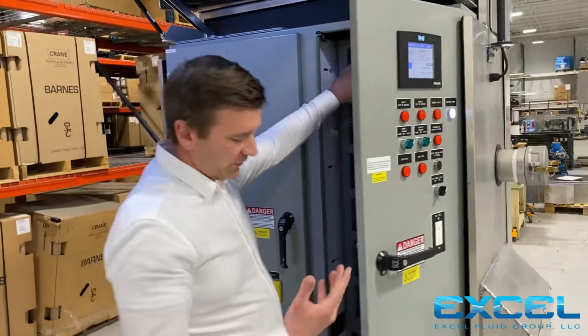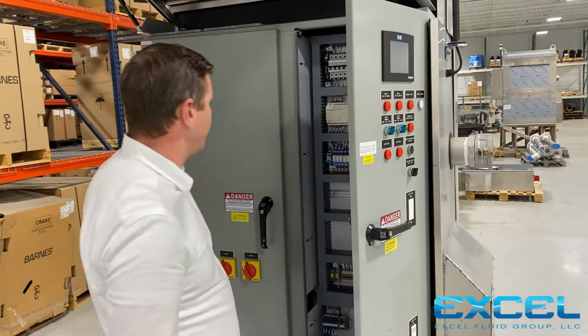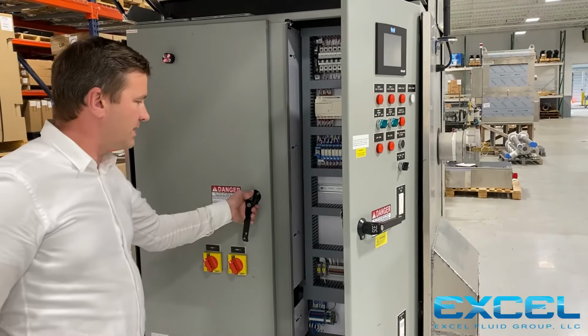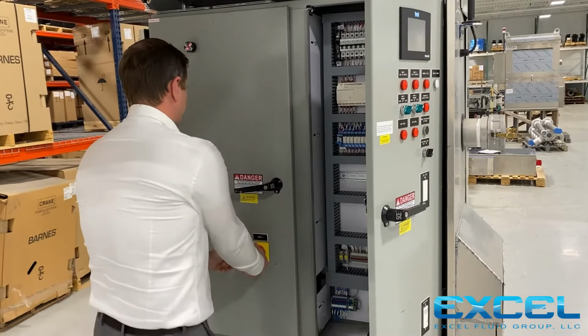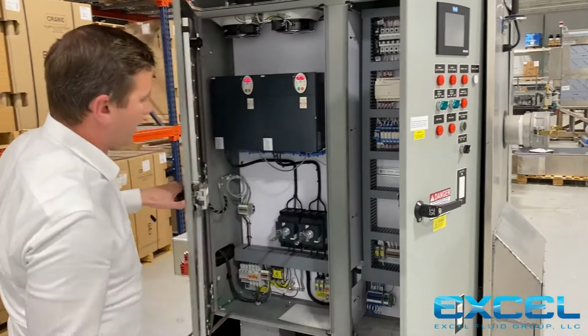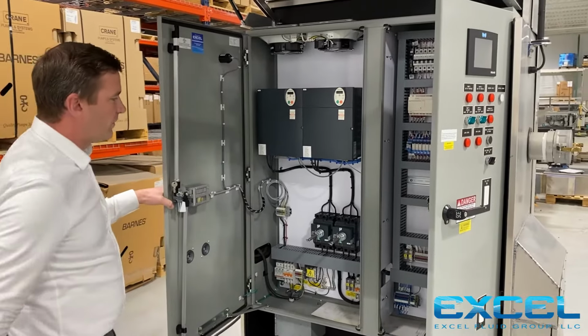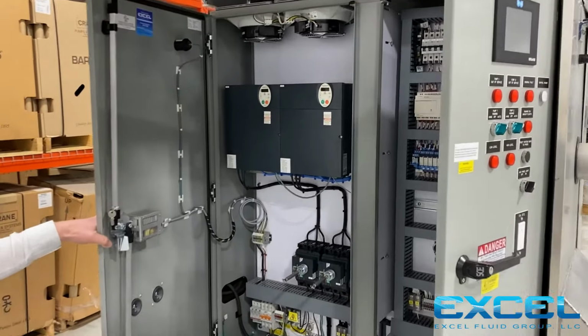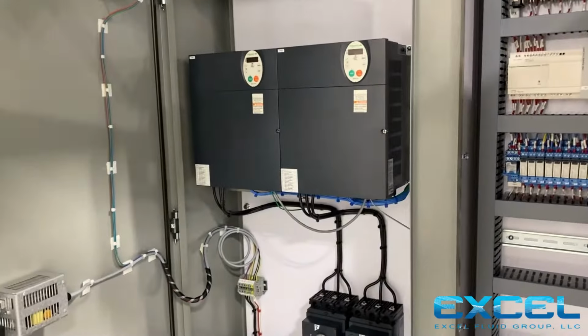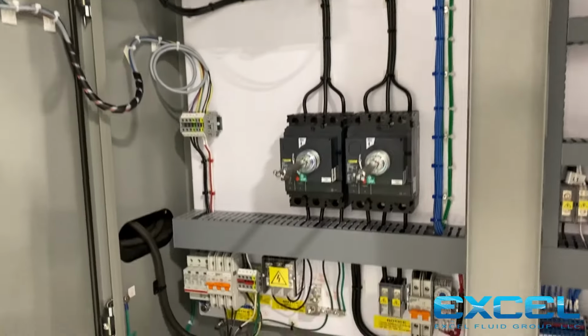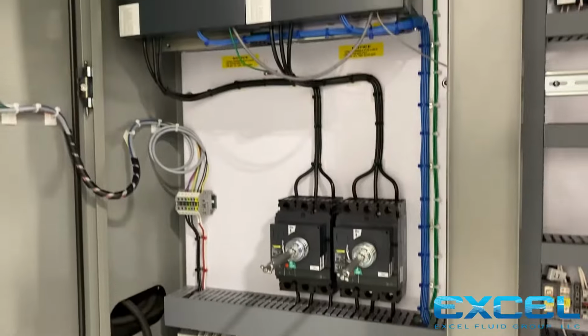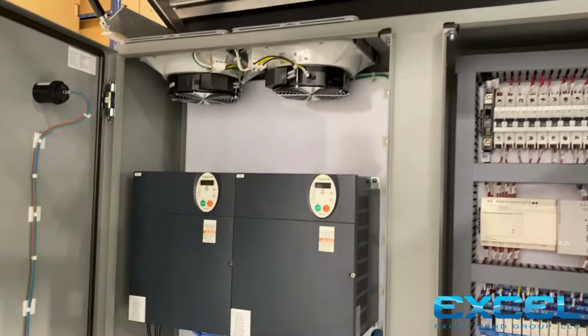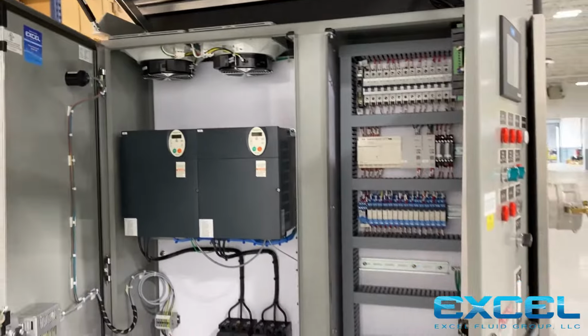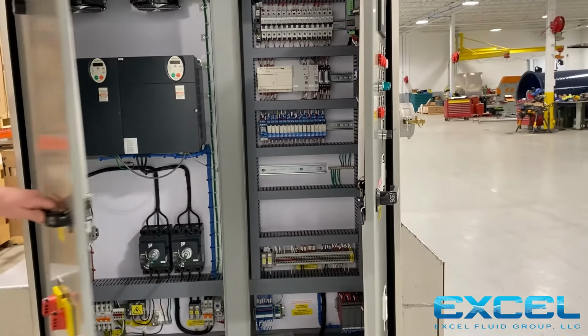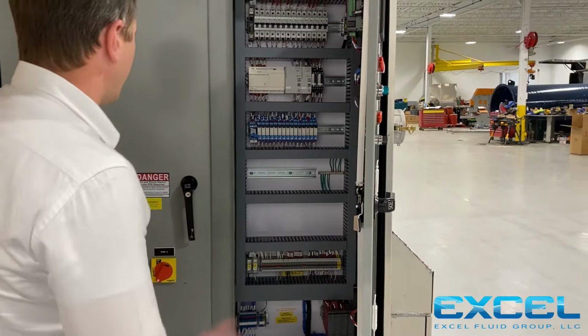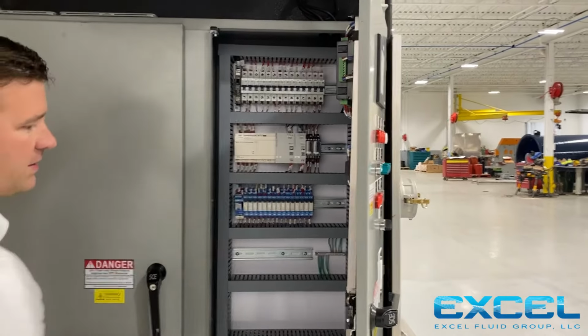We have a switch in here just for the demonstration unit. Typically you do this outside. I shut power off. That gets me access to the high voltage side. Oh, I gotta turn my pumps off. Now I can get access to the high voltage side. In this case, it's 2 variable frequency drives. Could be NEMA starters, could be soft starts. In a triplex system, it'd be a larger enclosure, you'd have 3. We'll bring in our float wiring in through intrinsically safe connection. A very, very safe control panel, eliminating arc flash hazards and keeping the operator in the low voltage side when that's all he needs to be doing.